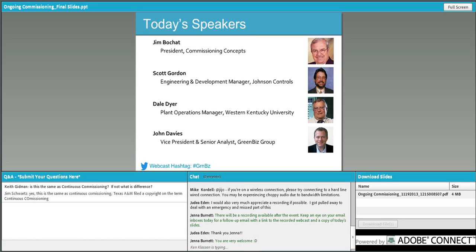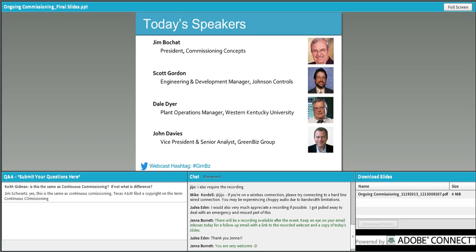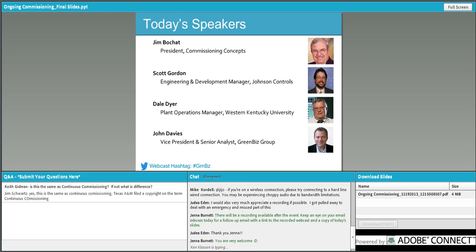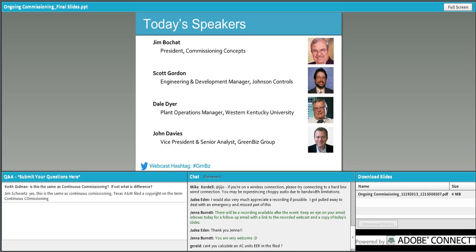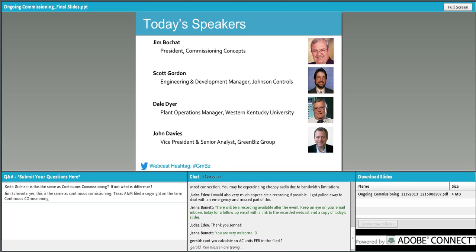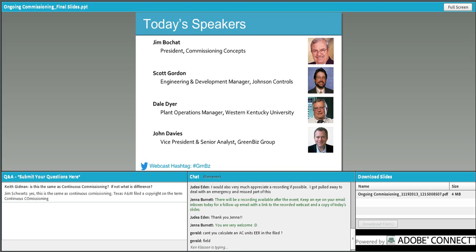That is a great question. And a follow-up before we switch over to Dale: we got another question about the efficiency curves that you showed. One of our attendees said manufacturers don't seem to publish them. Is there a way for people to get to those efficiency curves? Right, that can be a challenge. If you can get the model and serial number on a chiller and contact the local supplier of that chiller, sometimes the data isn't put into a curve format. It may be in a table format showing percent load and kW per ton or COP, and often entering condenser water temperature. There's a lot of variables involved there. So from that table format, you can convert it over into a curve.